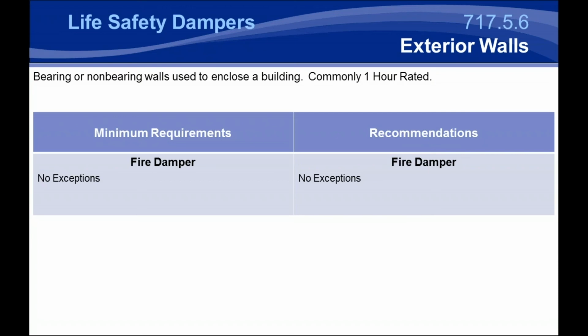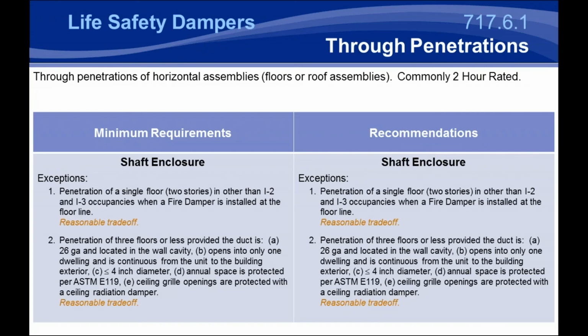that you are allowed. Typically, because of your openings for glazing and access into the building, whether it's equipment access or personnel access, you'll find that HVAC ducts are going to need to be protected by fire dampers because you've exceeded the amount of unprotected openings. Through penetrations are a little different, and basically we're not talking about damper requirements here, but shaft requirements. And basically this is when shafts are needed versus when shafts are not needed.